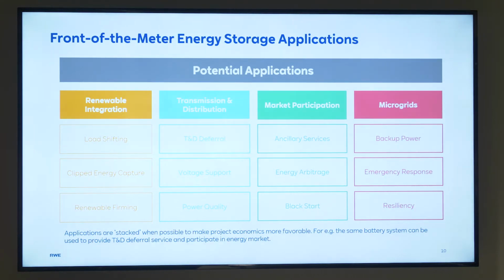For clipped energy, batteries can be charged with excess solar output when the solar inverter hits its peak rating and would otherwise begin clipping or not producing. We can take that energy, clip it, and store it for use at a later time. For firming and smoothing, the last one, this is the most common application where we can further enhance the output of a solar project, since solar projects are really only efficient on cloudless, sunny days.